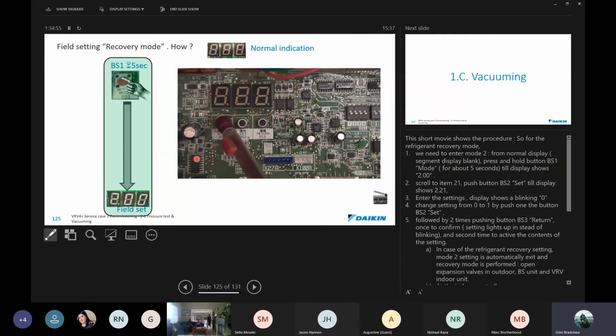I'm going to hold down BS1 first, get into mode 2, and then BS2 until you get to 21. BS3, 0, BS2 to 1, and then twice on BS3, and the unit will come up tier 1. When it shows you tier 1, you can go check your indoor remote controllers, and all of those should show that they're in test mode. Then they're locked out; you can't do anything to them when they're in that mode. When they're like that, all the expansion valves in the system, including the BS boxes on a heat recovery system, will open up. You can now perform a recovery pressure test or evacuate the system.